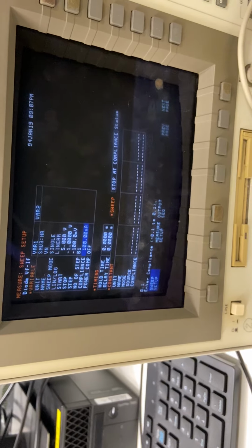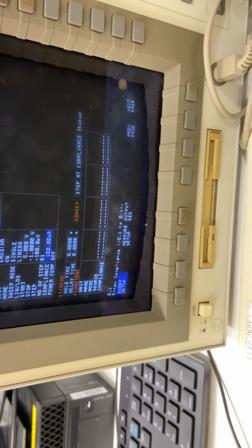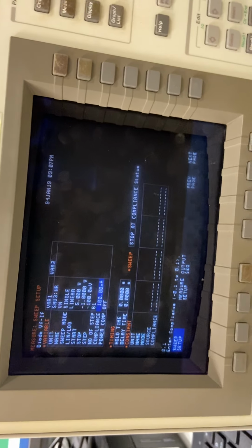For the diode measurement, compliance is probably not too much of a problem. But if you're measuring, for example, a transistor, you will not expect the gate current to be very high. In that case, you can set a compliance on the gate current so that even if the gate leaks, your device will not be burned. Essentially, that's what it is. Even in this case, for the diode measurement, you can put a compliance there.